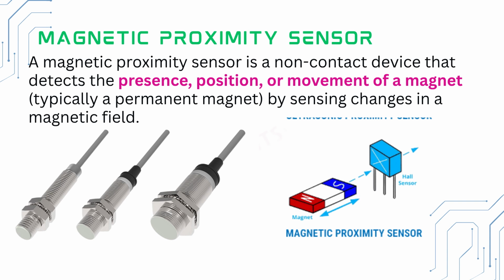Typically, those are permanent magnets, by sensing the changes in the magnetic field. Unlike inductive sensors that detect only metal, this requires a magnetic target but offers significantly longer sensing ranges, up to 70 millimeters or more, relative to their small size.